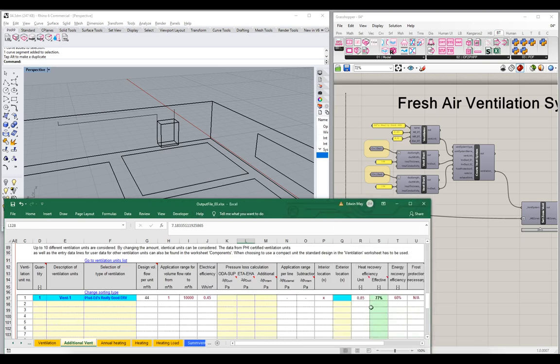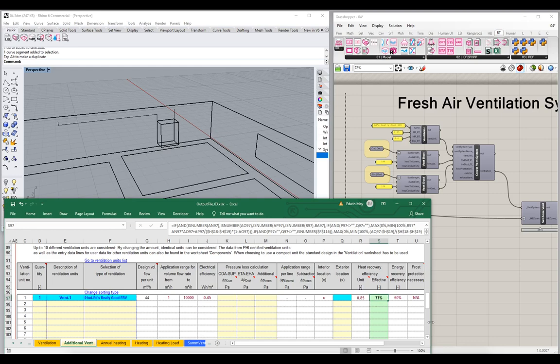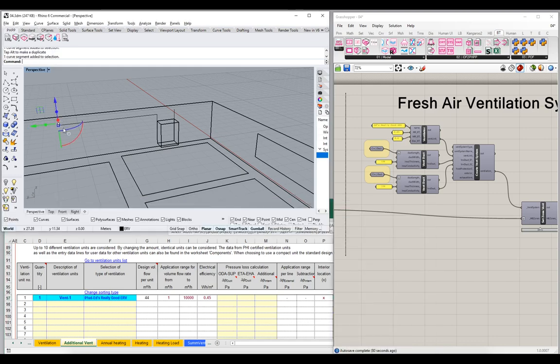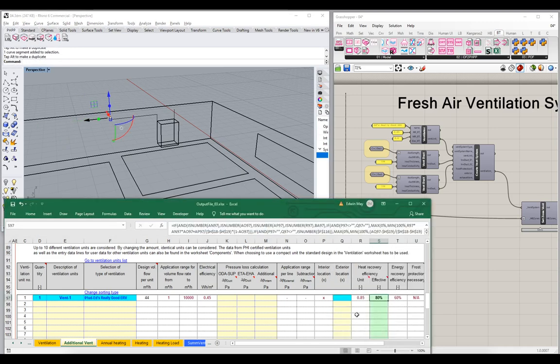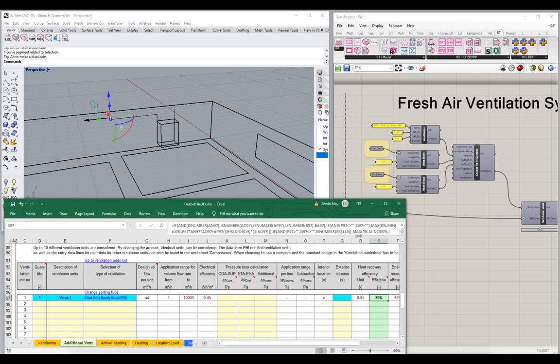Our system efficiency now jumped up to 77% — we went from 72 up to 77%. If we were to bring the duct back down to more like a 10-foot separation instead of a 20-foot separation, that bumped us up to 80%. So changing the length of those ducts is really meaningful — it changes the amount of heat loss pretty substantially on a small project like this. It can make a big difference both in terms of the output surface temperature of the air coming out of the HRV, as well as the overall heat loss.